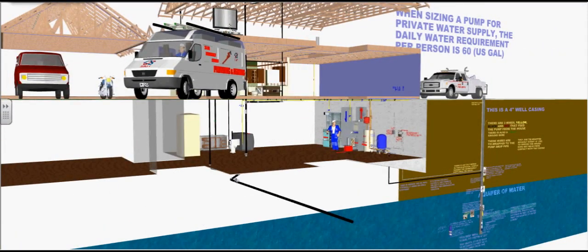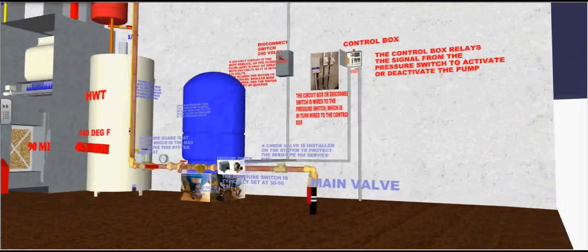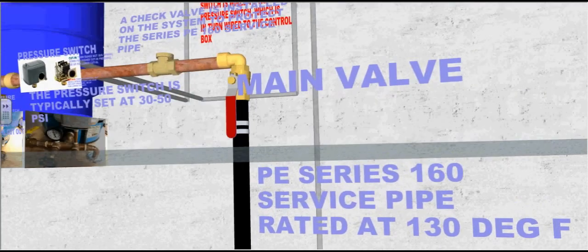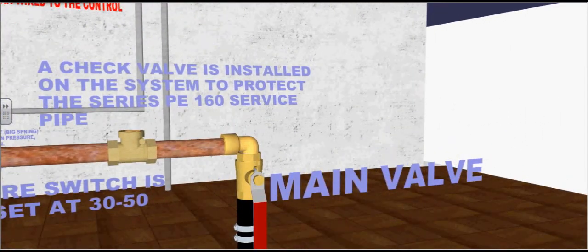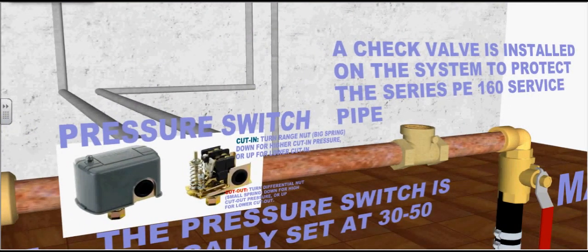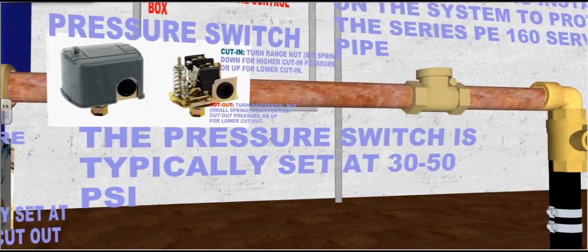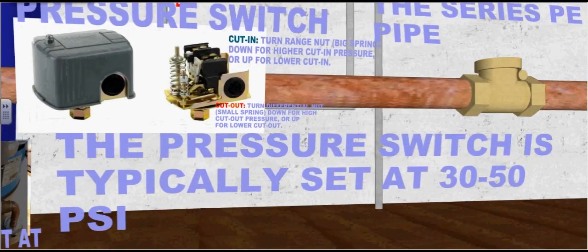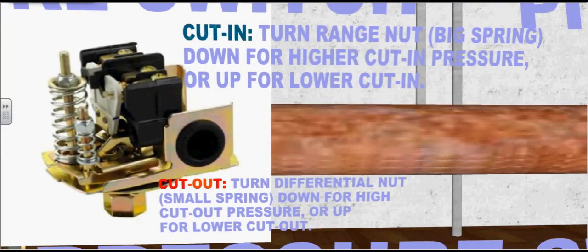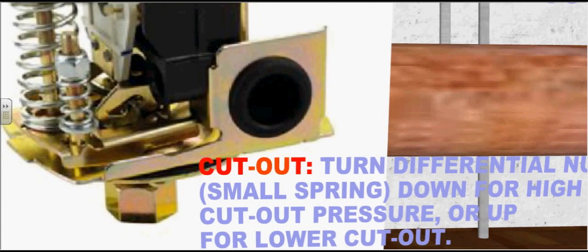Now we will go into the mechanical room and follow the polyethylene pipe, which is double clamped to the main valve. A check valve is installed on the system to protect the series 160 polyethylene service pipe. A pressure switch is installed, typically set at 30 to 50 PSI. To adjust the pressure switch, go to the big spring — the cut-in spring. Turn the range nut down for higher cut-in pressure or up for lower cut-in pressure. Adjust the small spring by turning the differential nut down for high cutout pressure or up for lower cutout pressure.